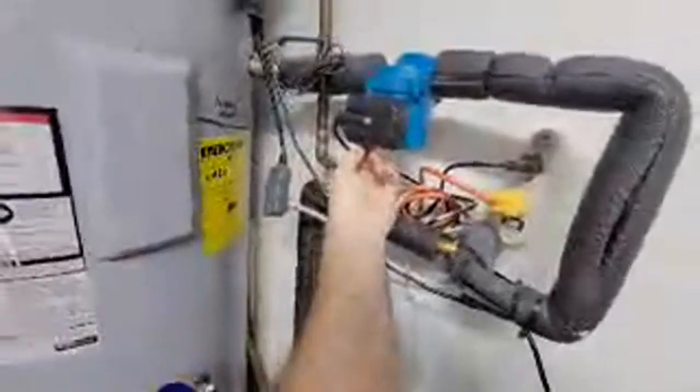Yeah, it's 118, but yes, I can hold my hand on there. When it really gets going, man, you can't even hardly hold your hand on there when it gets the water temperature going. I actually have the water flow as slow as this goes, but I need to do a couple tweaks on it. You can increase the compressor RPM. Well, that's the thing. I have a fixed speed rotary in that, and that's what's haunting me right now.